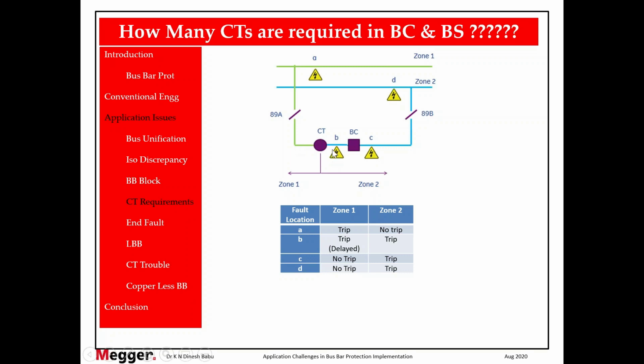So after a fault occurs in location B, zone 2 trips the breaker, all the bays connected to zone 2 along with the bus coupler. The moment the bus coupler opens, the CT will be eliminated from zone 1. This is another way of looking at it. But in reality, once the breaker is open, the CT will be eliminated from the differential calculation. It's not like end fault protection, where we monitor the current using breaker feedback. That is also a different way of doing it. But what we are doing is eliminating the CT from the zone 1 calculation based on the bus coupler status. So the bus coupler operation time is actually the delay.